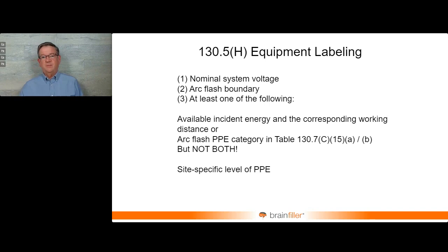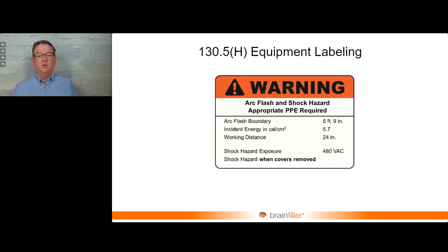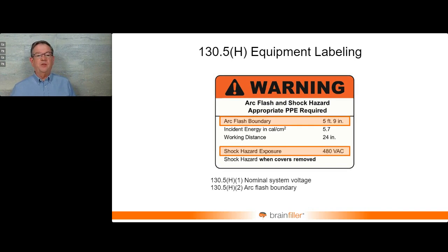So if you're of the time when people like to talk about category 2 and 4, just call it level 2, level 4. My preference today is to put the arc rating on the label, because that's all anybody really cares about. I don't care if it's 2.3, 3.4, or whatever. I want to know, what do I wear? 8 calorie PPE? So that's the better way, in my opinion, to go about it. So as a minimum, you have to have the voltage, the boundary, and at least one of the following: a method to identify how you're going to select the PPE.